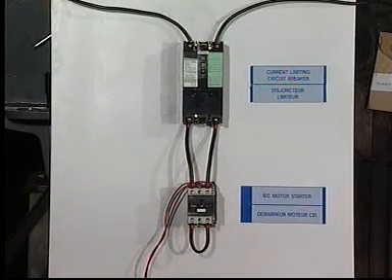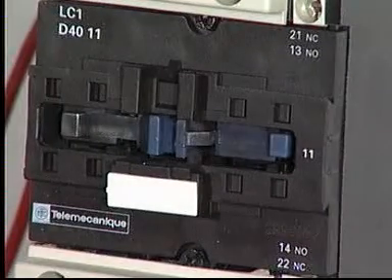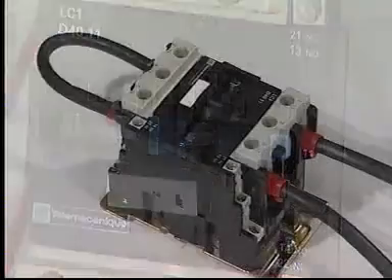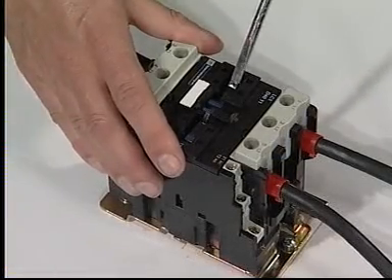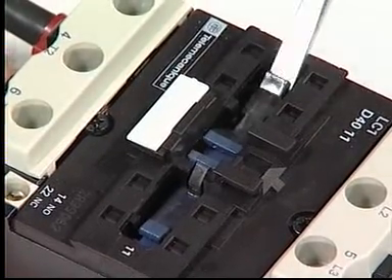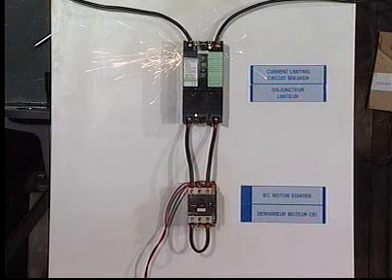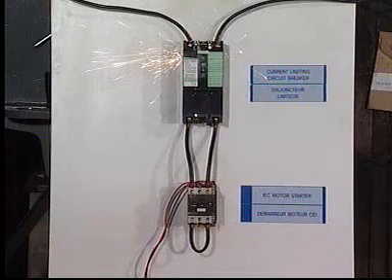Although the amount of outgassing is significantly reduced, the starter contacts again appear to be welded. Upon closer inspection, it was determined that the contacts were unable to be pried open. With a freeze frame, it can be seen that the actual fault energy has been reduced. Nevertheless, the protection level remains Type 1 protection.